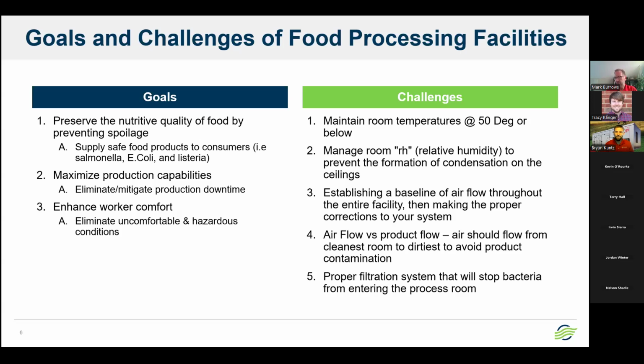So some key challenges that we typically face are maintaining room temperatures at or below 50 degrees, ideally 45 degrees, especially in your proteins. Reason being, any environment that is above 50 degrees is prone to promote the growth of bacteria. So ideally, we do want to see most of these rooms under 50 degrees. Not all of them do fall in that category, but some of the critical ones certainly do. And then along with that is managing the moisture in the room. So we're talking relative humidity, we're talking dew point, which we'll touch on a little bit here today when Mark starts to talk about the technical side of things.